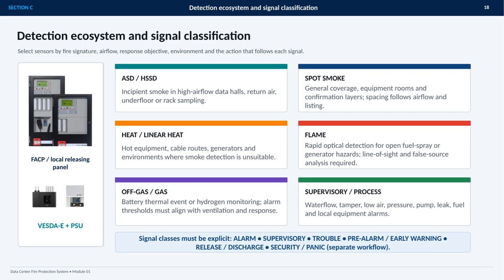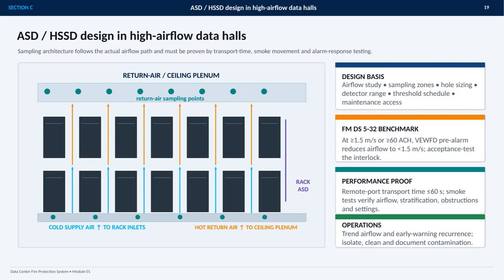Supervisory and process signals include water flow, tamper, low air, pressure, pump, leak, fuel, and local equipment alarms. Signal classes must remain explicit: alarm, supervisory, trouble, pre-alarm or early warning, release or discharge, and security or panic, which follows a separate workflow. This slide focuses on designing aspirating smoke detection, or ASD, and high-sensitivity smoke detection, or HSSD, for data halls with significant airflow.